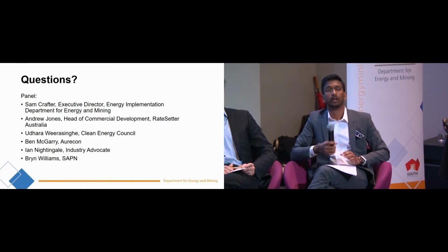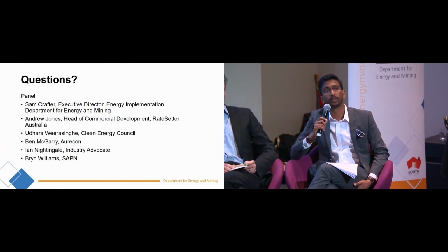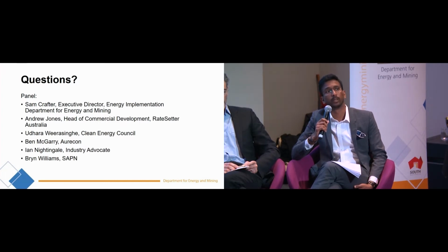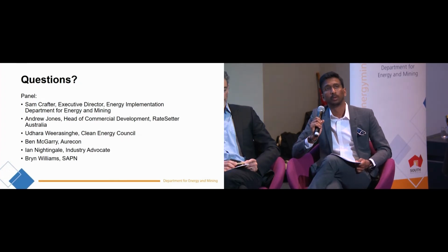Okay, so our state and the CEC are comfortable with where this is going with no Australian standard? Well, actually, IEC 62619 was directly adopted as an Australian standard end of last year. And so that is actually an Australian standard, IEC 62619 2017. That is a lithium secondary cell storage safety standard. But there's no Australian standard or IEC standard for BMS, for lithium management systems.